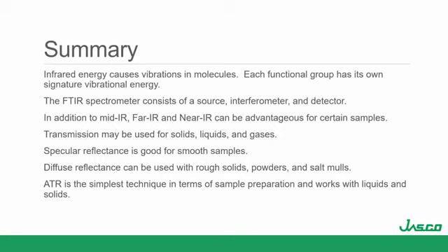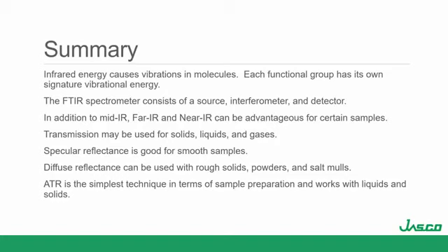Specular reflectance is good for smooth samples. Diffuse reflectance can be used with rough solids, powders, and salt mulls. And ATR is the simplest technique in terms of sample preparation, and works with liquids or solids. And I thank you for your time and will take any questions.